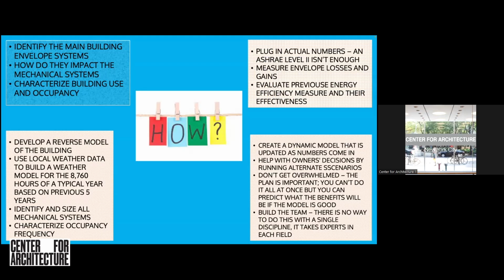Plug in the actual numbers. ASHRAE level 2, which is what's referenced in the building code and by most of these programs for building retrocommissioning, it's not enough. It's very mechanical system centric. It tells you to do an evaluation of the building envelope, but it doesn't really tell you how, other than determining whether the windows are dual glazed or single glazed. It's very basic stuff - you need to drill down more than that.